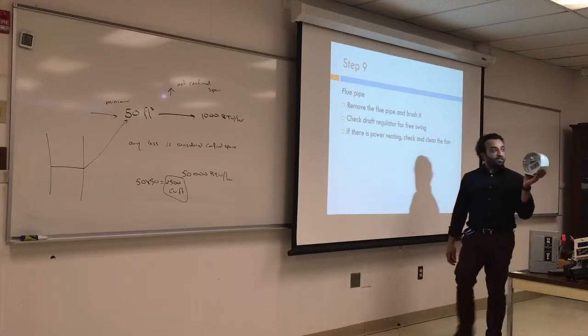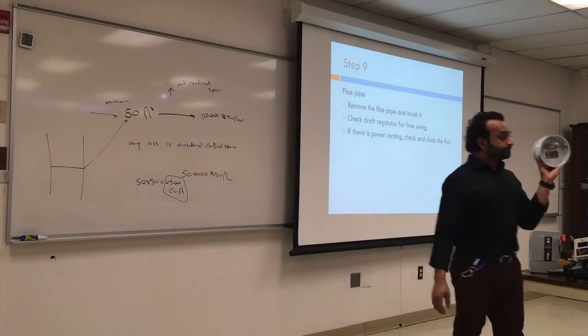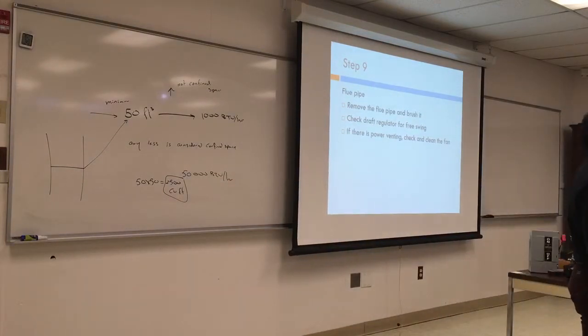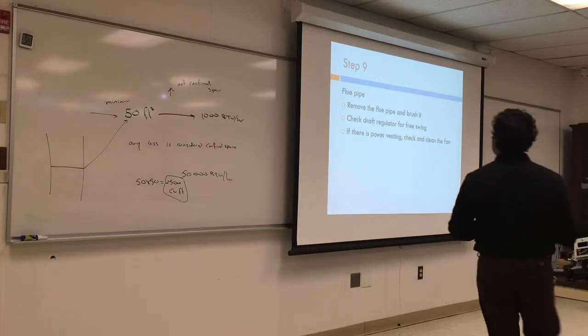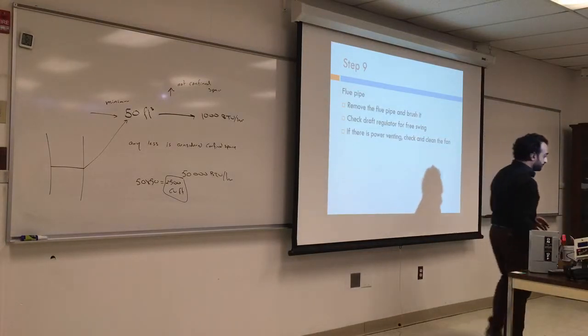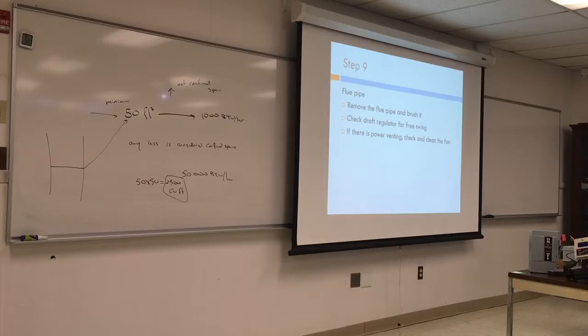So this should be closed naturally. It should tilt a little bit once the burner is on. If you come in and the burner is off and it's open this way, that means it's faulty. It should be balanced. It should be naturally closed. And make sure you push on it and it moves freely without being stopped. That's a free swing, right? Yep. And if there's power venting, check and clean the fan.